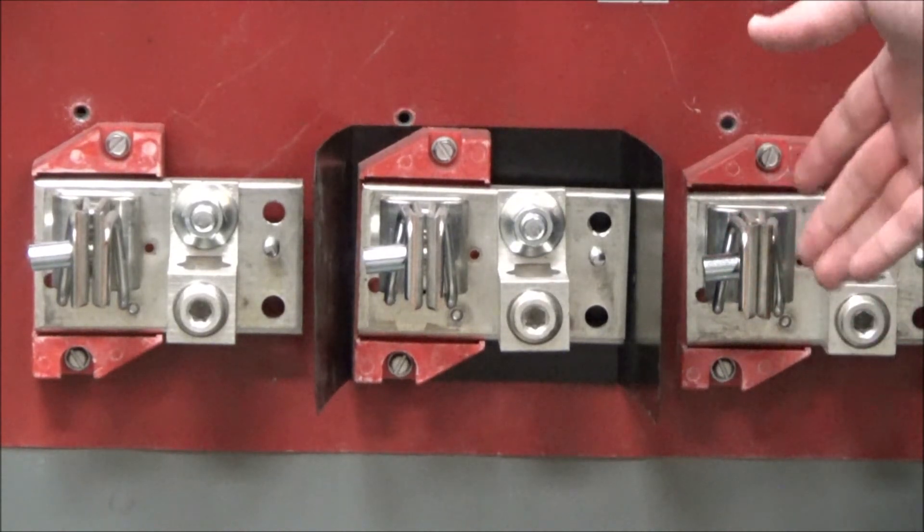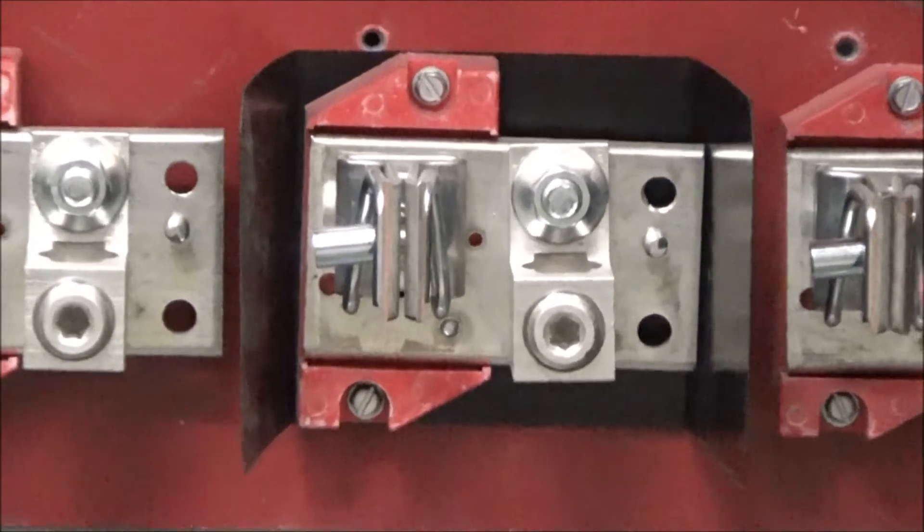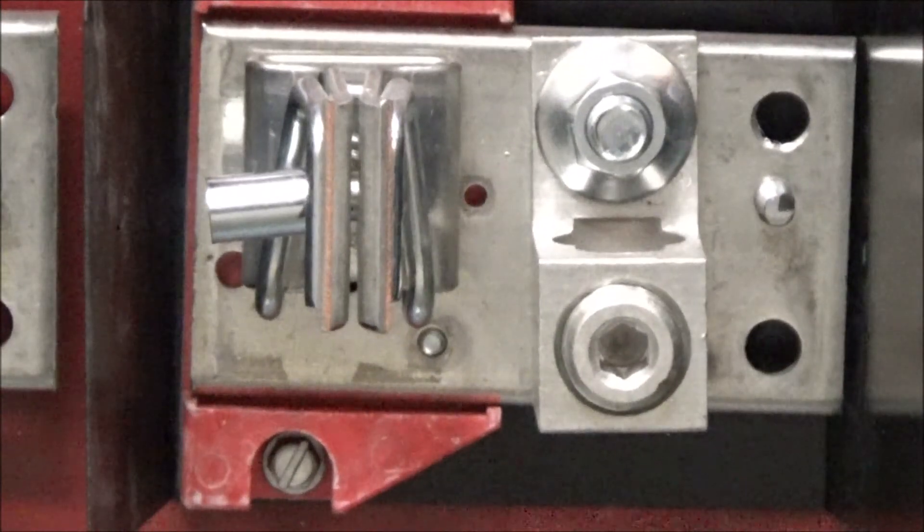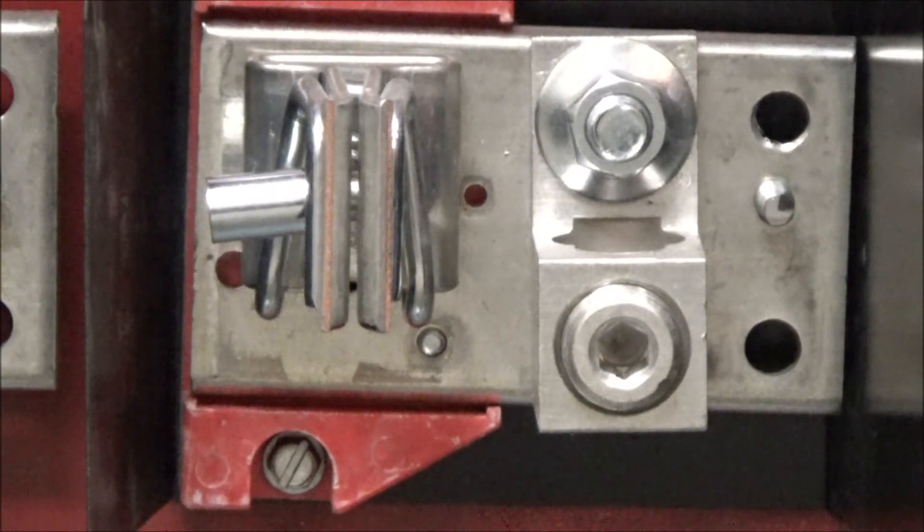Once you have all three installed your switch will now only accept class R fuse kits. Note that once the collar is pushed onto the pin it cannot be removed.